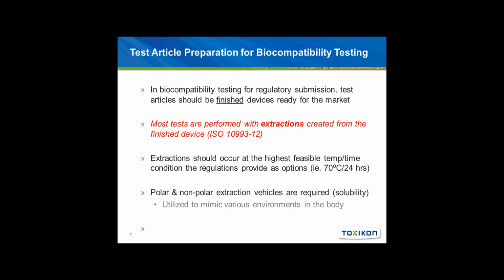That means we have considered all of the manufacturing processes. We are using the devices with the additives that will be present. We have the packaging considered and already incorporated into the process. We have sterilization, a very key aspect, already conducted on the device, so that if there's going to be any effect to the material or the device, that's captured in our test article and then appropriately assessed in our biocompatibility testing. So most tests that are performed for biocompatibility are performed with an extract created from these finished devices.